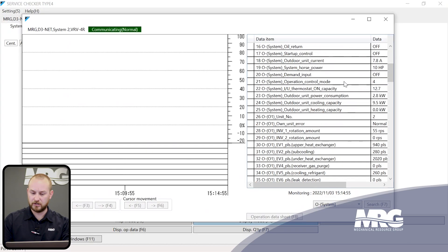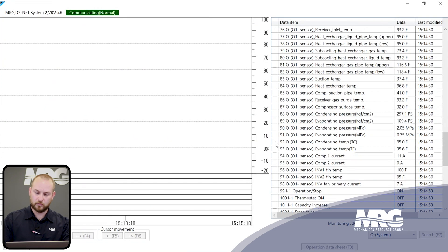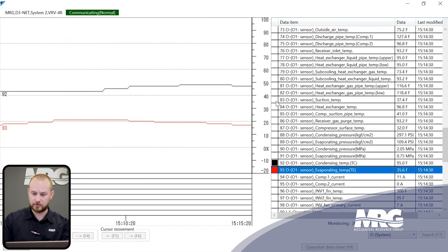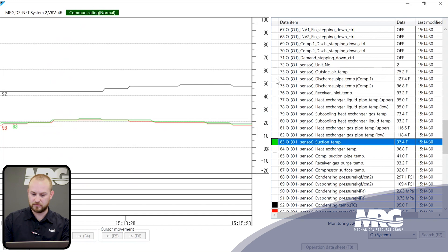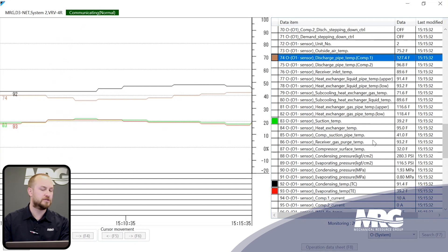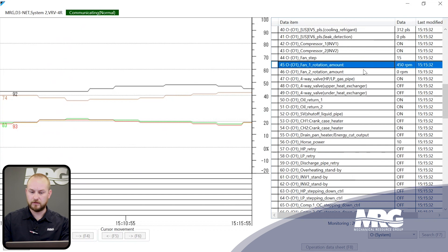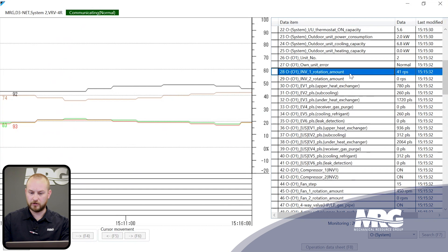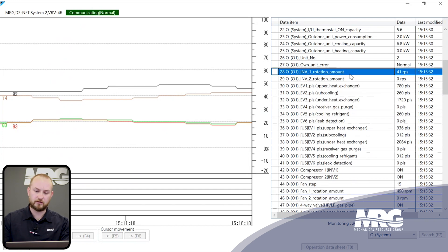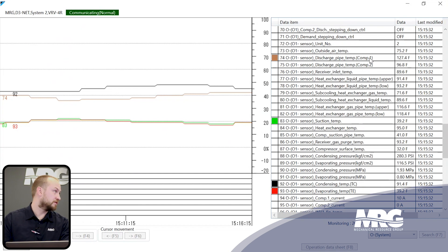Scrolling through the data, we're looking for discharge pipe temperature, condensing and evaporating temperatures, and suction temp. From those we can calculate suction superheat and discharge superheat — both very critical when diagnosing a liquid flood back condition. We can also see which compressors are running: right now compressor inverter one is on at 41 revolutions per second, and compressor two is off.